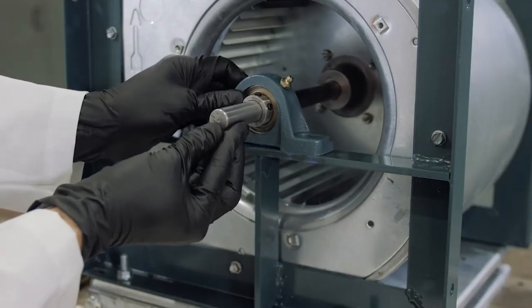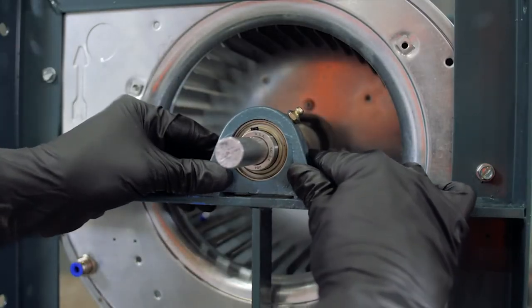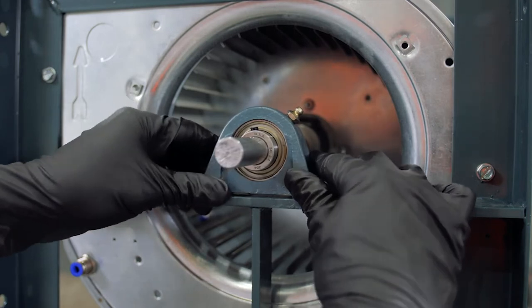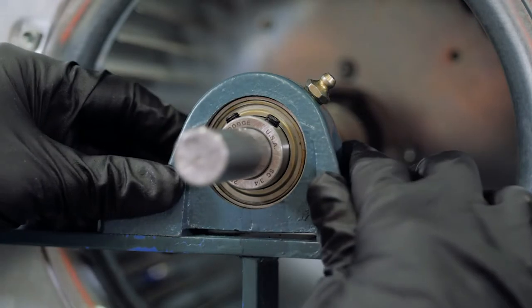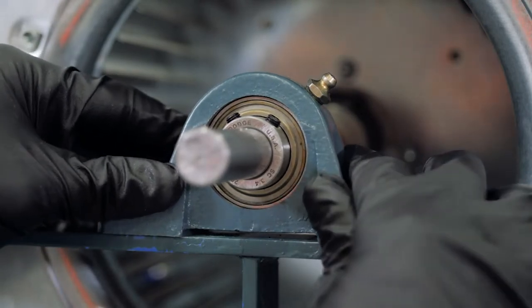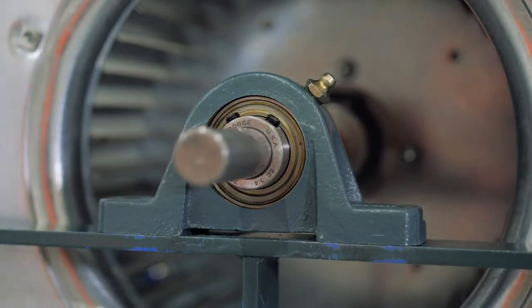Proper alignment is important to maximize the life of the bearing. Dodge ball bearings are rated for plus or minus two degrees of static misalignment. A bearing may be aligned using the shaft to position the insert relative to the housing or by fixing the insert with the shaft and adjusting the housing.